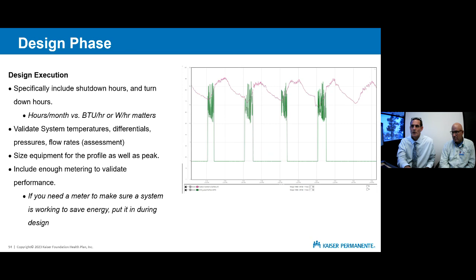I've mentioned it a couple times now, we literally have almost a checklist of stuff we can look at during design that are energy measures. I want to emphasize these are not things that add a ton of cost to the project. These are things where we look at the system we're serving, look at the control points we're serving, and see what we can do. Nobody's getting above ceilings or pulling permits. A lot of this is programming-only changes: check all the set points, check all the minimums on the VAV boxes, check the operating hours and non-operating hours, that sort of stuff. There's a lot of that we can do during almost all of our HVAC designs.